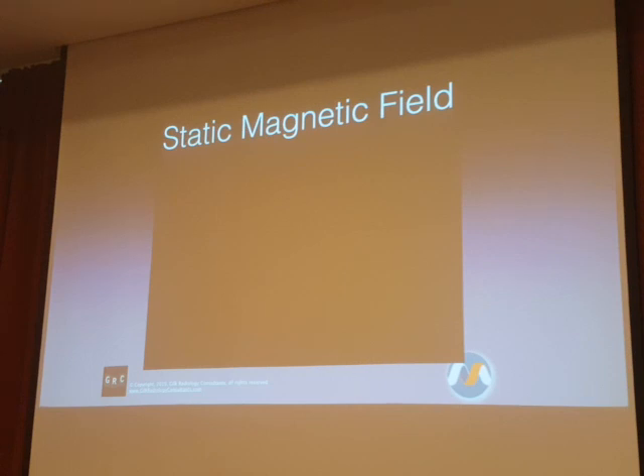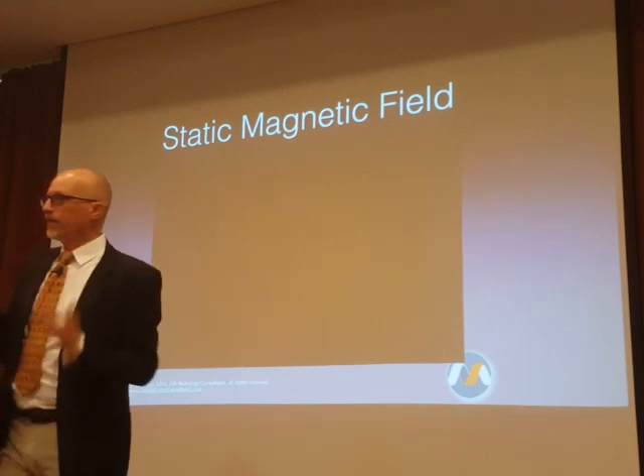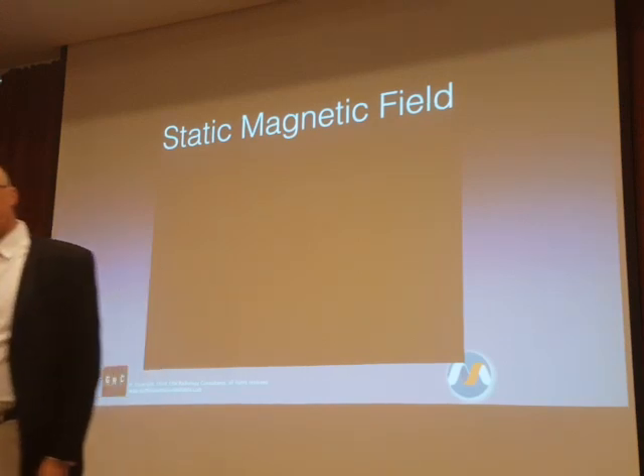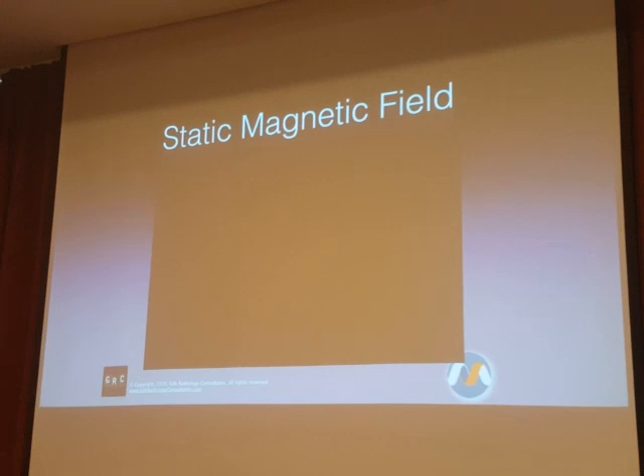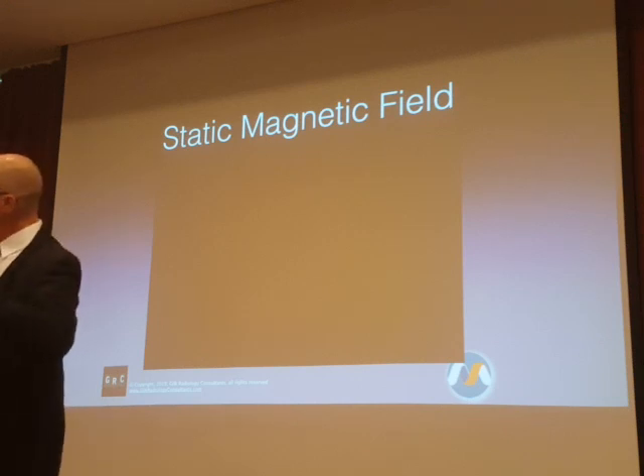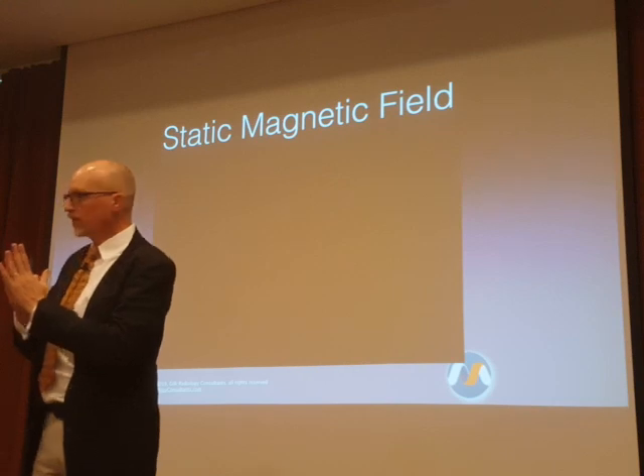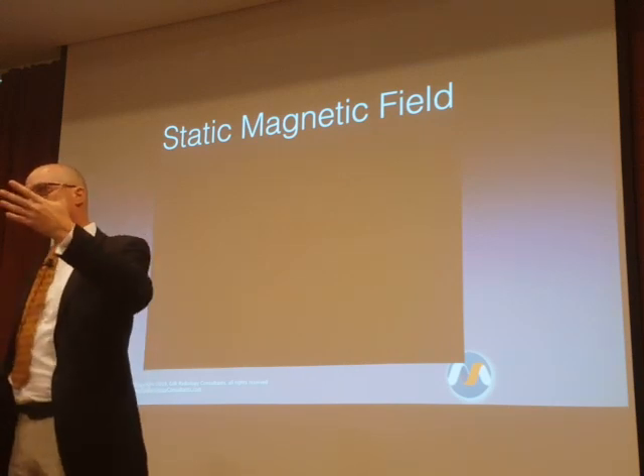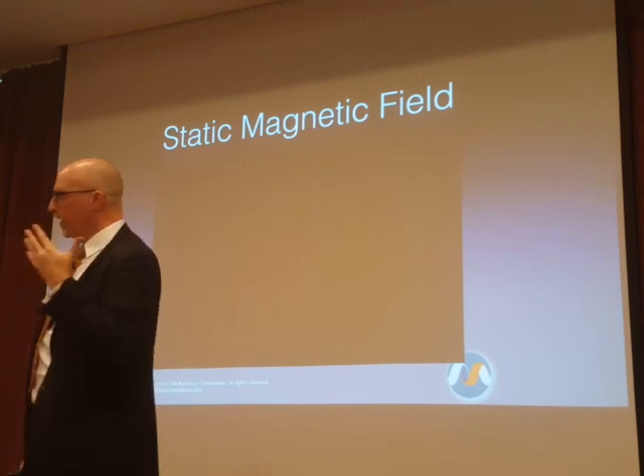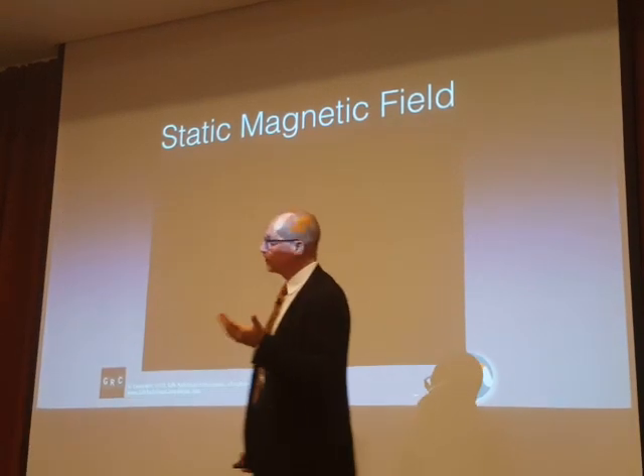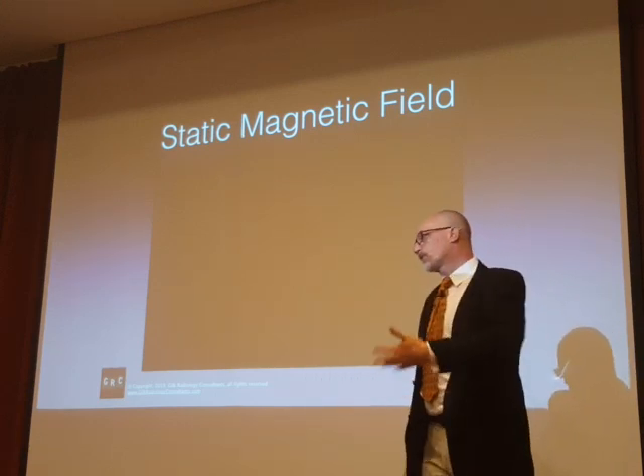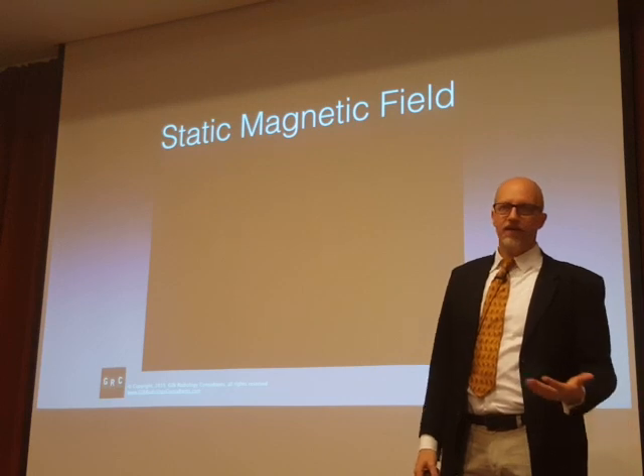Today, because active shielding in MRI scanners is so much better than it used to be, what it means today with that same object is, as I walk towards the magnet, I feel nothing, I feel nothing, I feel nothing. Whoosh, it's gone. Without any meaningful period of feedback to tell me that something is changing. Active shielding compresses the magnetic field, which means there's an alarmingly higher spatial gradient, a much steeper spatial gradient. This can lull us into a false sense of security if we step through the doorway into the MRI scanner room and we don't feel anything.